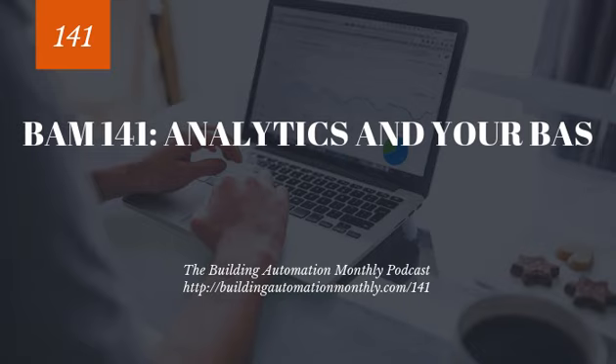And so you can actually look at the thermal load in a building dynamically if you're watching how many people badge in and out of the building. Now, if that just completely blew your mind, like you're like, what the hell is this guy talking about? What I was saying essentially is that while you can have these fault detection diagnostic algorithms, and they can simply look at system performance, they can also take in external variables like how many people are in the building, which location is the sun at, what percentage is it at, where are shade positions, et cetera, in order to determine the environmental effects on system performance.